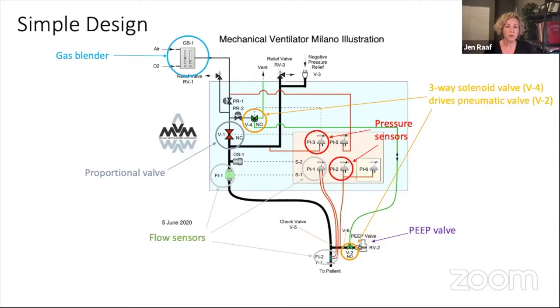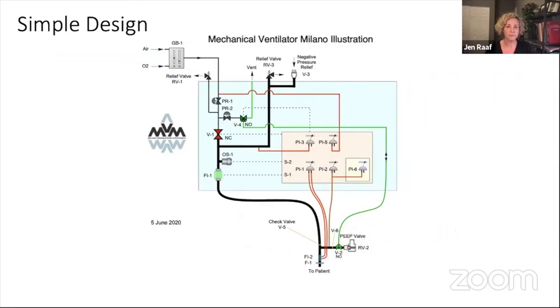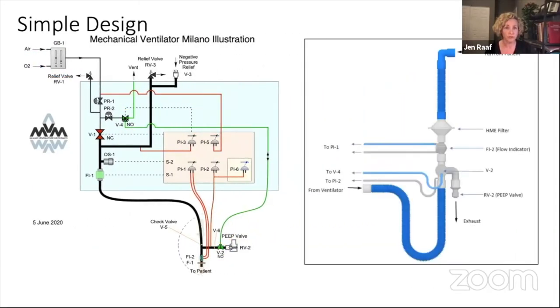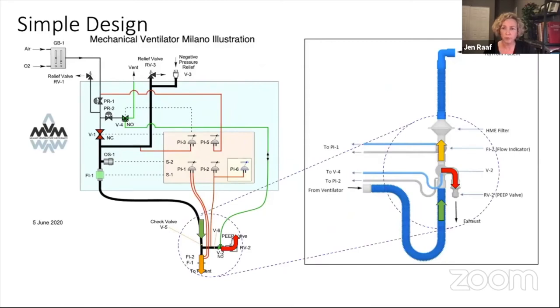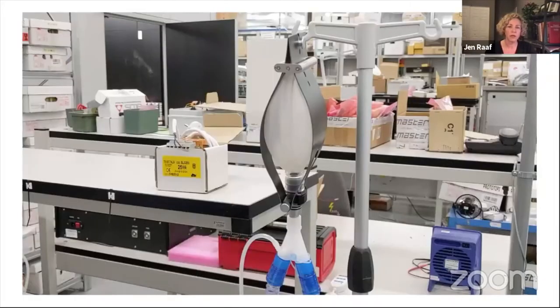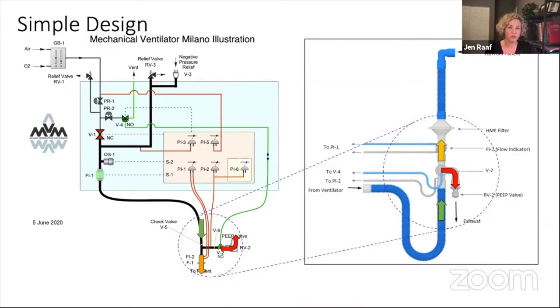All of this equipment at the bottom is external to the ventilator—everything I've circled in purple. It's part of the breathing circuit shown at the right, where the patient is attached to the machine up at the top here, and all these other little tubes are attached into the ventilator to measure the pressures and provide the airflow.